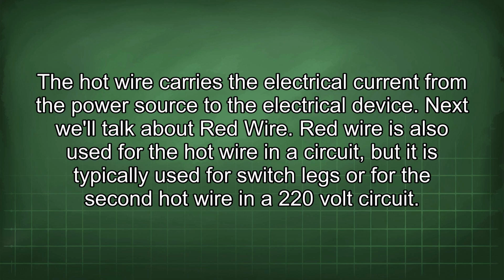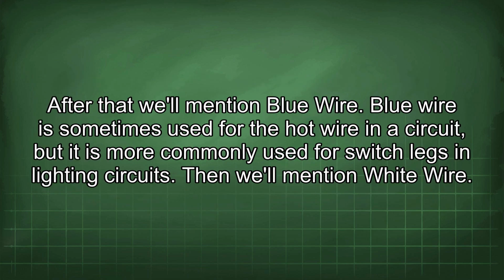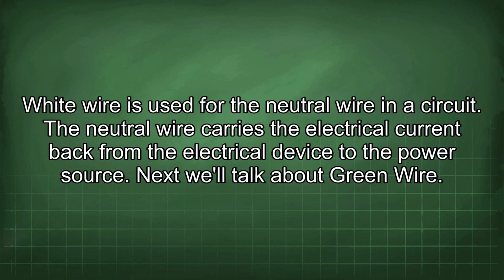Next, we'll talk about red wire. Red wire is also used for the hot wire in a circuit, but it is typically used for switch legs or for the second hot wire in a 220-volt circuit. After that, we'll mention blue wire. Blue wire is sometimes used for the hot wire in a circuit, but it is more commonly used for switch legs and lighting circuits. Then we'll mention white wire. White wire is used for the neutral wire in a circuit. The neutral wire carries the electrical current back from the electrical device to the power source.